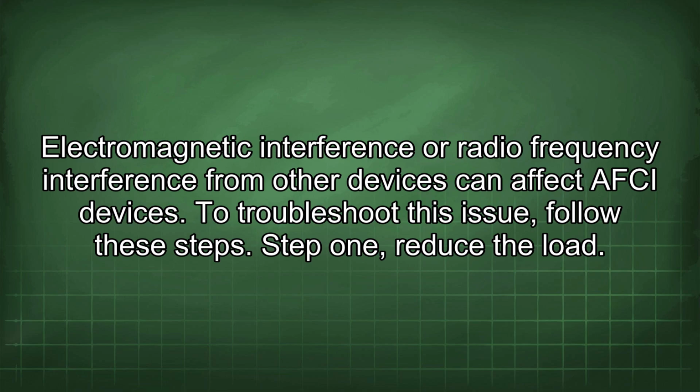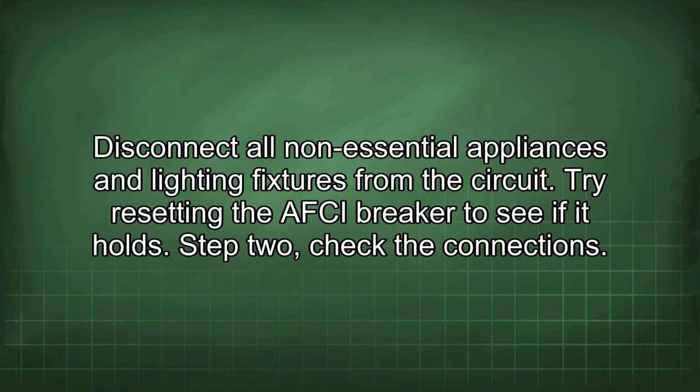To troubleshoot this issue, follow these steps. Step 1. Reduce the load. Disconnect all non-essential appliances and lighting fixtures from the circuit. Try resetting the AFCI breaker to see if it holds.